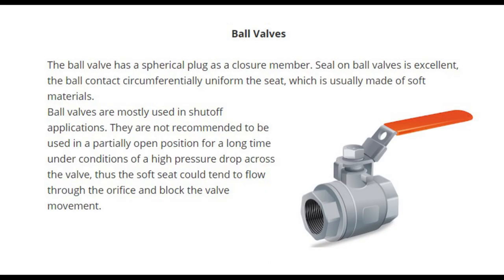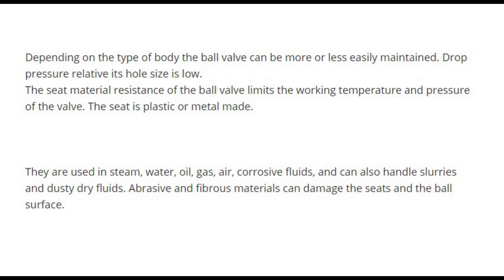Ball valves have a spherical plug as a closure member. The seal on ball valves is excellent — the ball contacts the seat circumferentially and uniformly, and the seat is usually made of soft materials. Ball valves are mostly used in shut-off applications. They are not recommended in a partially open position for a long time under high pressure drop conditions, as the soft seat could tend to flow through the orifice and block the valve movement. Pressure drop relative to hole size is low, and the seat material limits the working temperature and pressure.